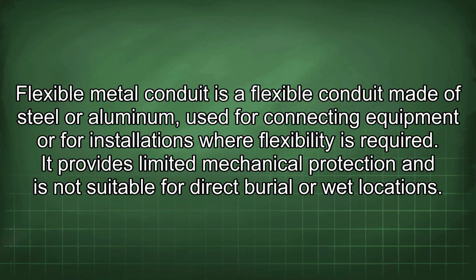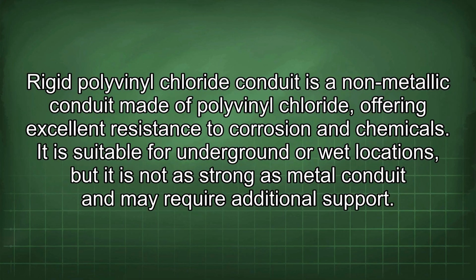conduit. Flexible metal conduit is a flexible conduit made of steel or aluminum, used for connecting equipment or for installations where flexibility is required. It provides limited mechanical protection and is not suitable for direct burial or wet locations. Rigid polyvinyl chloride conduit is a non-metallic conduit made of polyvinyl chloride, offering excellent resistance to corrosion and chemicals.